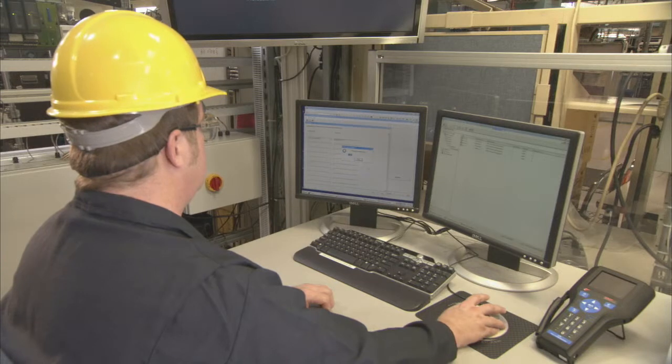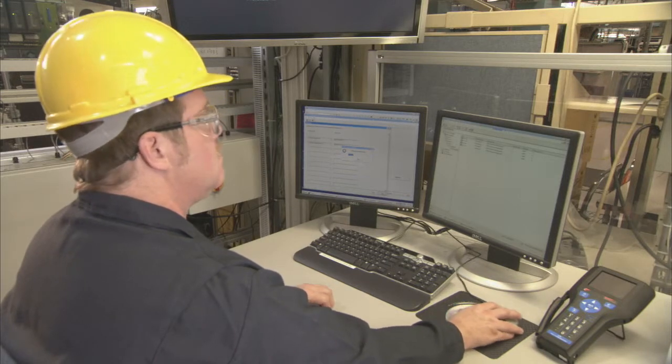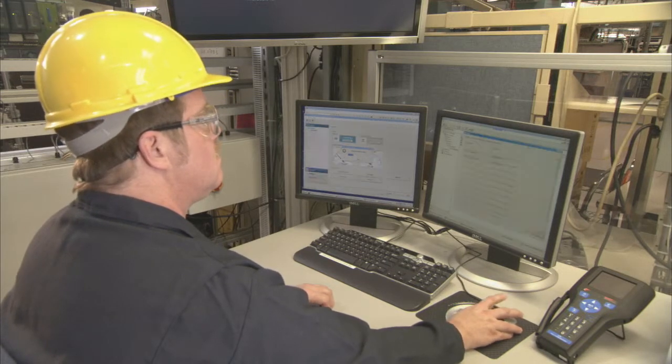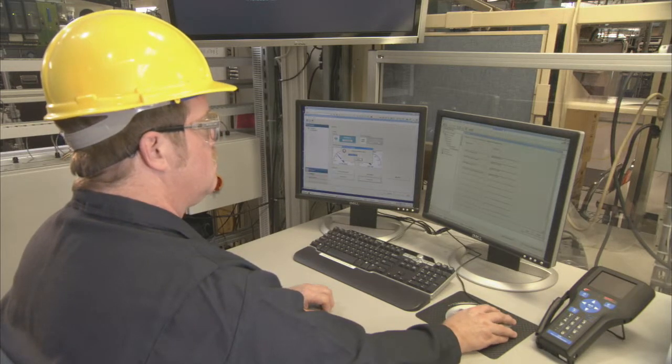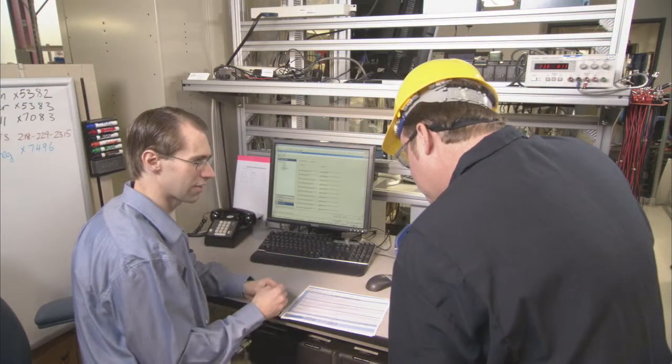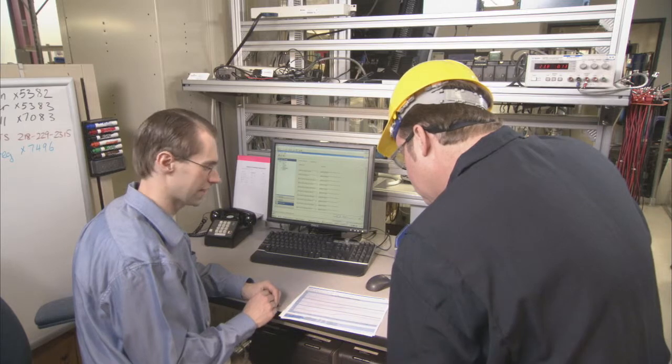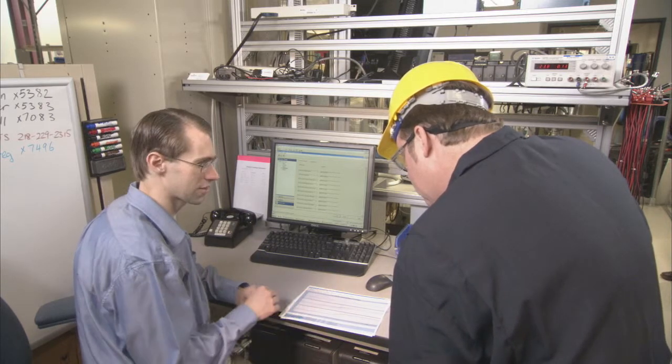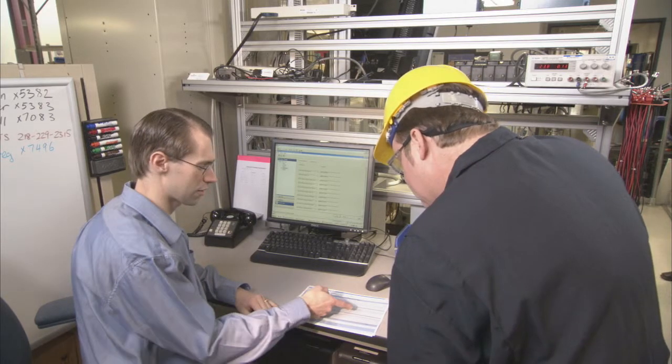With the diagnostic status log, the technician can now check the history of the transmitter to better understand the device condition and then decide if a trip to the field is necessary. A process engineer can also use this log to correlate events with a historian to better diagnose issues relating to the process. The diagnostic status log can help you be more productive in troubleshooting the device and process, as well as saving you trips to the field.